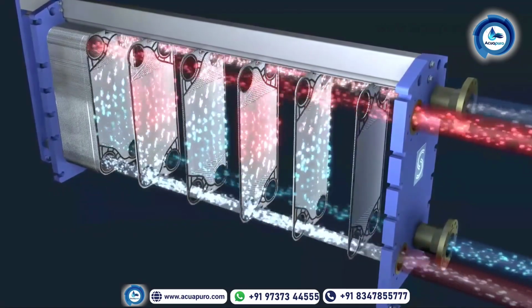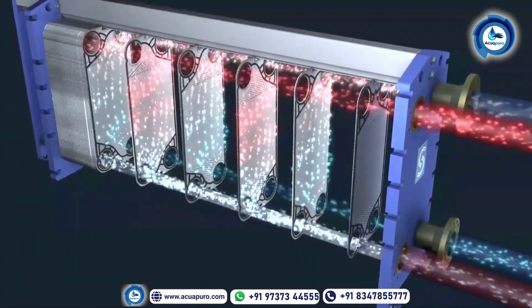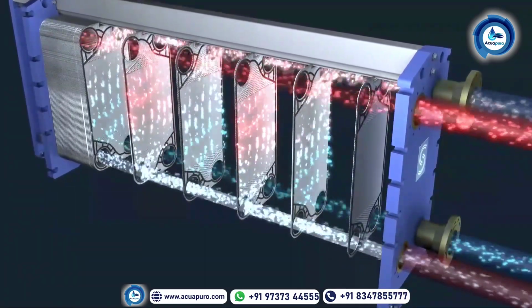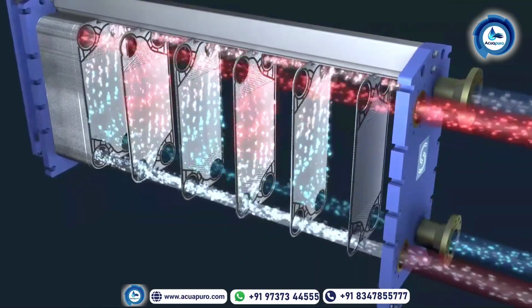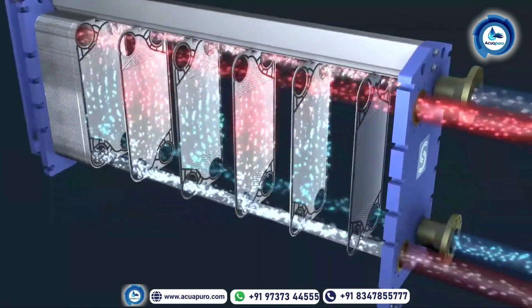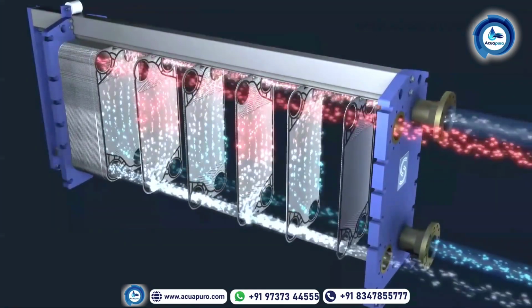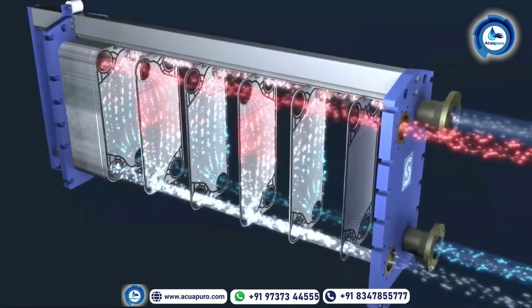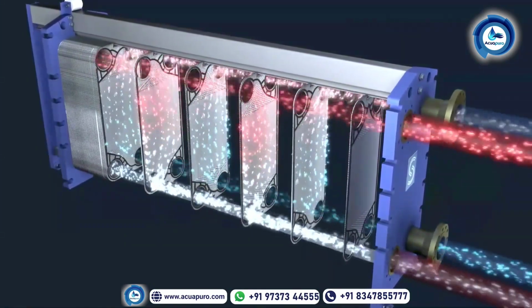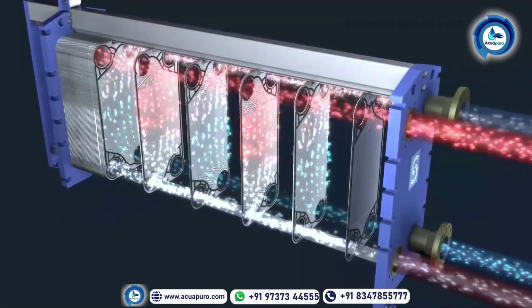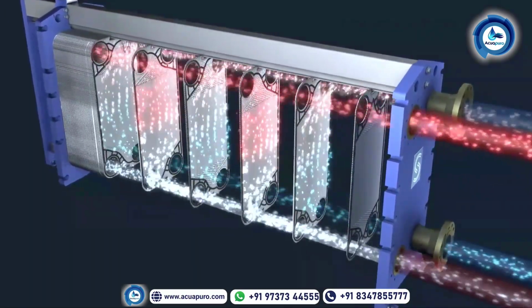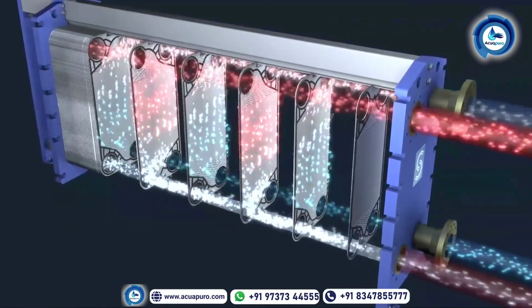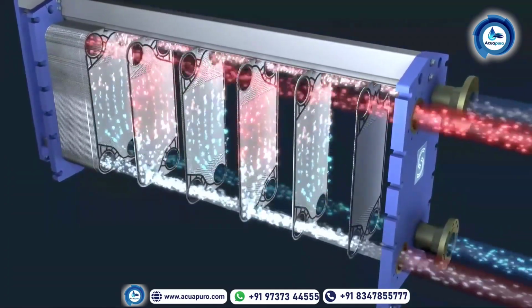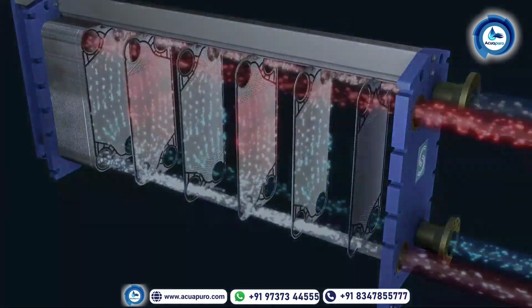Here we are going to put the inlet and outlet connection of your pure material. And the S3 and S4 you have to connect to the cooling tower. So the cooling tower will reduce the temperature of your material. Let's suppose that your inlet temperature will be nearby 75 to 80. So after this plated heat exchanger, without mixing fluid, your product material should be nearby 35 to 40.